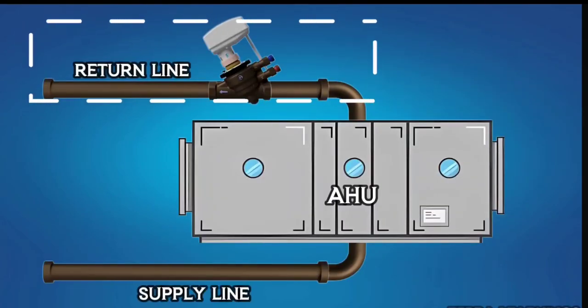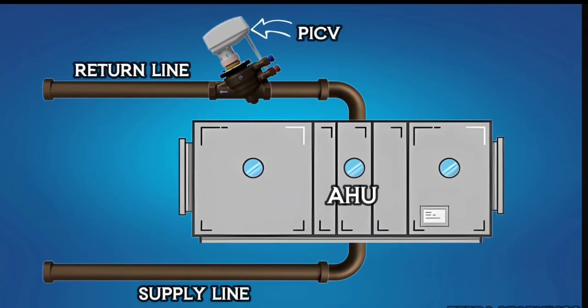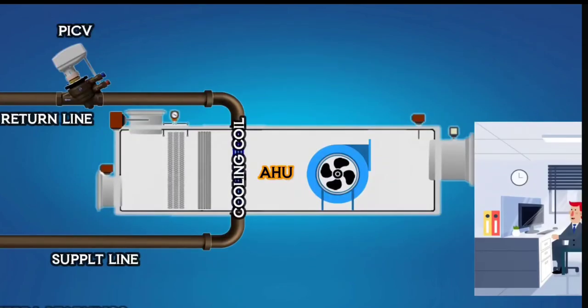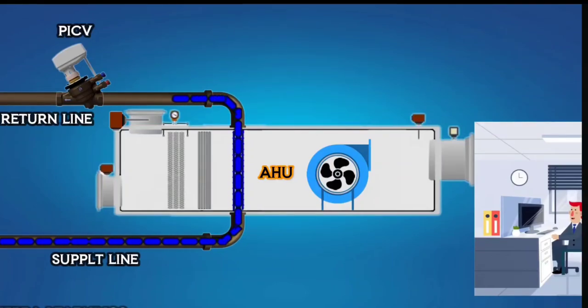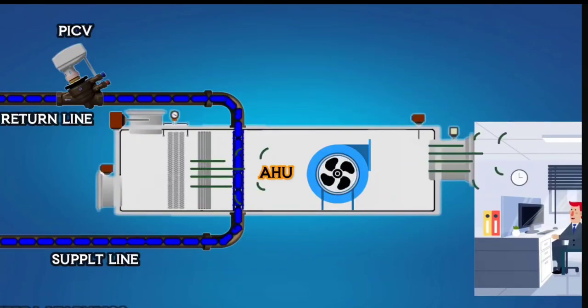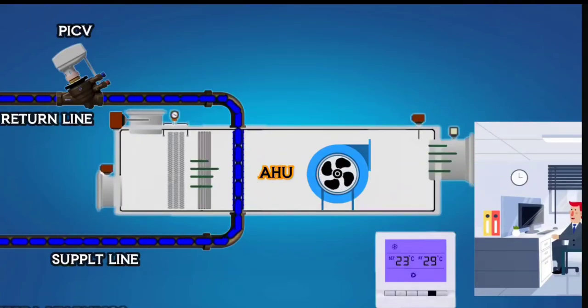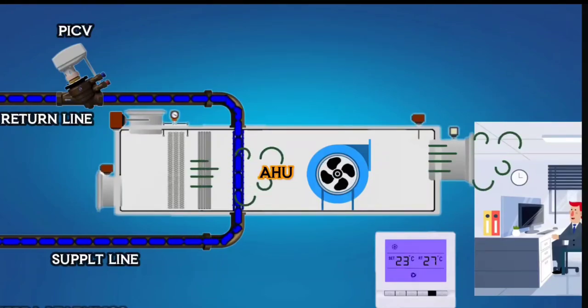PICV is installed in the return line of the AHU. It is a common interview question to ask about the placement of PICV in an AHU system. PICV is always installed on the return line. Chilled water enters the AHU's cooling coil through the inlet and exits through the outlet. As the chilled water travels through the cooling coil, the coil cools down. When the air passes through this coil, the air effectively cools and provides the comfortable temperature in the room.